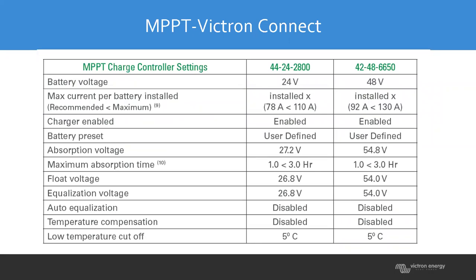We do see higher voltages than 54.8—if you're watching it, you might see a max of maybe 56 or so. But these set points we put in are just for a situation where we lose comm, so we can keep rolling. It's not going to be as efficient as closed loop, because at that point it's guessing the duration, the absorption voltages, the set times, and things like that.